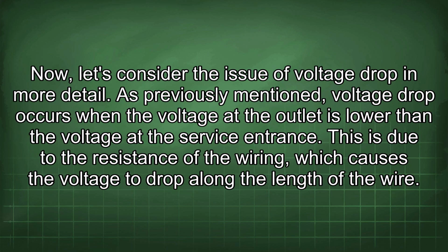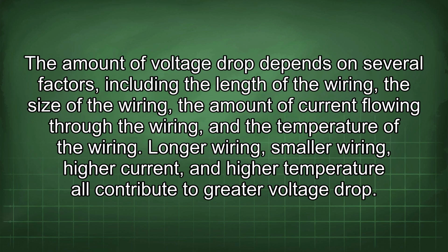Now let's consider the issue of voltage drop in more detail. As previously mentioned, voltage drop occurs when the voltage at the outlet is lower than the voltage at the service entrance. This is due to the resistance of the wiring, which causes the voltage to drop along the length of the wire. The amount of voltage drop depends on several factors, including the length of the wiring, the size of the wiring, the amount of current flowing through the wiring, and the temperature of the wiring. Longer wiring, smaller wiring, higher current, and higher temperature all contribute to greater voltage drop.